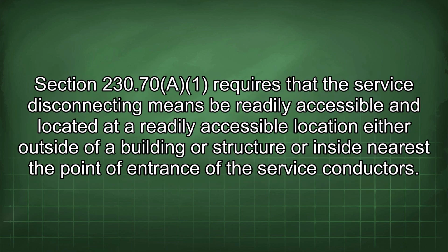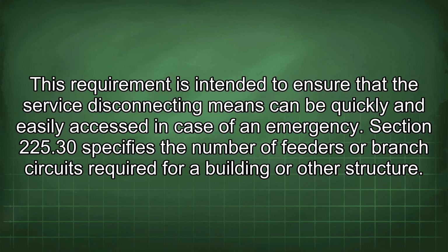Section 230.70(a) requires that the service disconnecting means be readily accessible and located at a readily accessible location either outside of a building or structure or inside nearest the point of entrance of the service conductors. This requirement is intended to ensure that the service disconnecting means can be quickly and easily accessed in case of an emergency. Section 225.30 specifies the number of feeders or branch circuits required for a building or other structure.